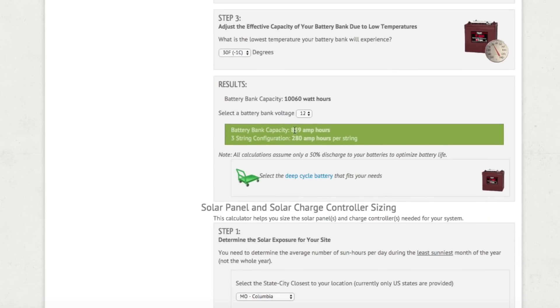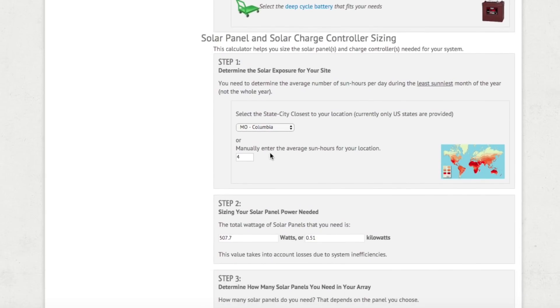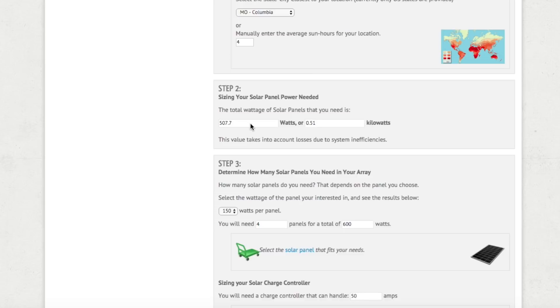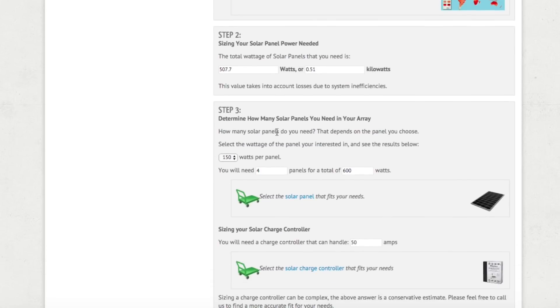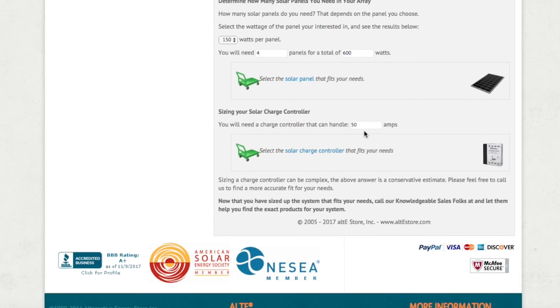After recalculating, you'll notice the results are much different. Instead of about 1,090 amp-hours of battery, we only need 819 amp-hours. When it comes to solar panels, instead of needing 660 watts, we only need 507 watts — reducing the number of panels from five 150-watt panels down to just four, which is exactly what we have on our system. The solar charge controller only needs to handle about 50 amps of current instead of 63 amps, just from removing that one hair dryer.